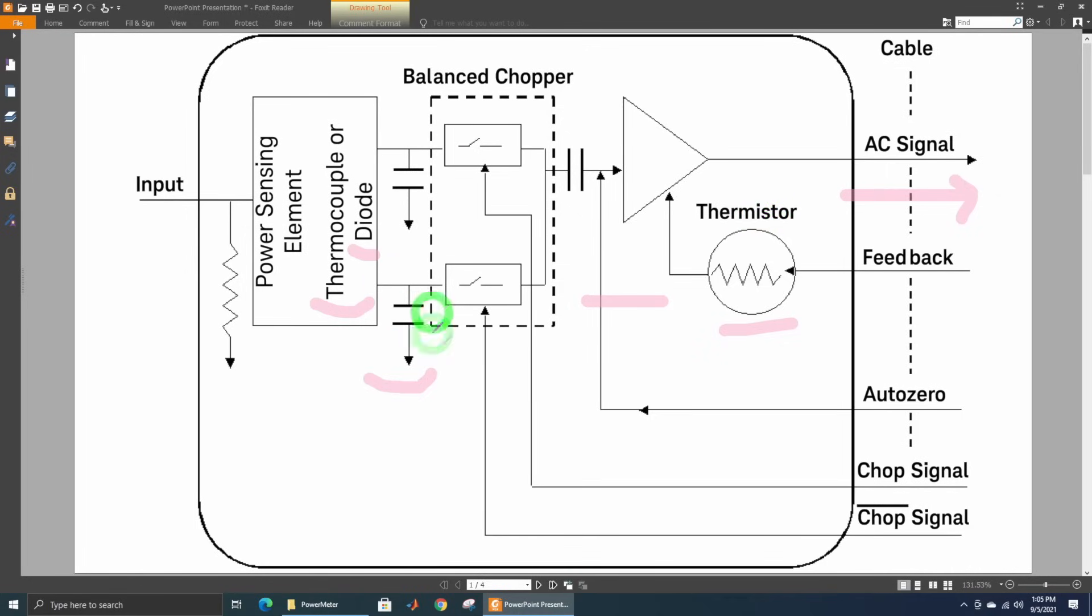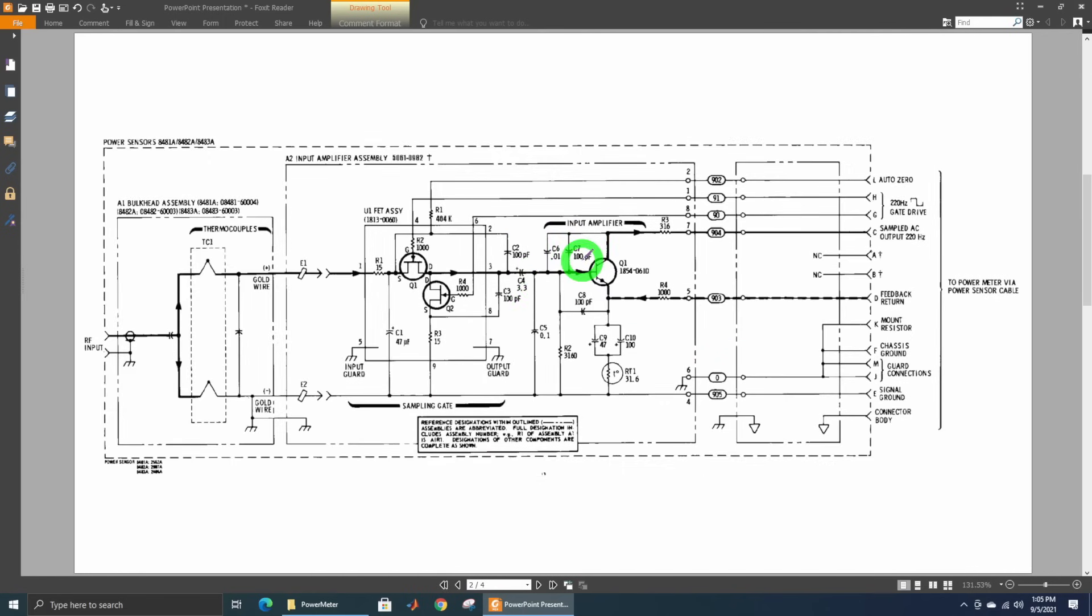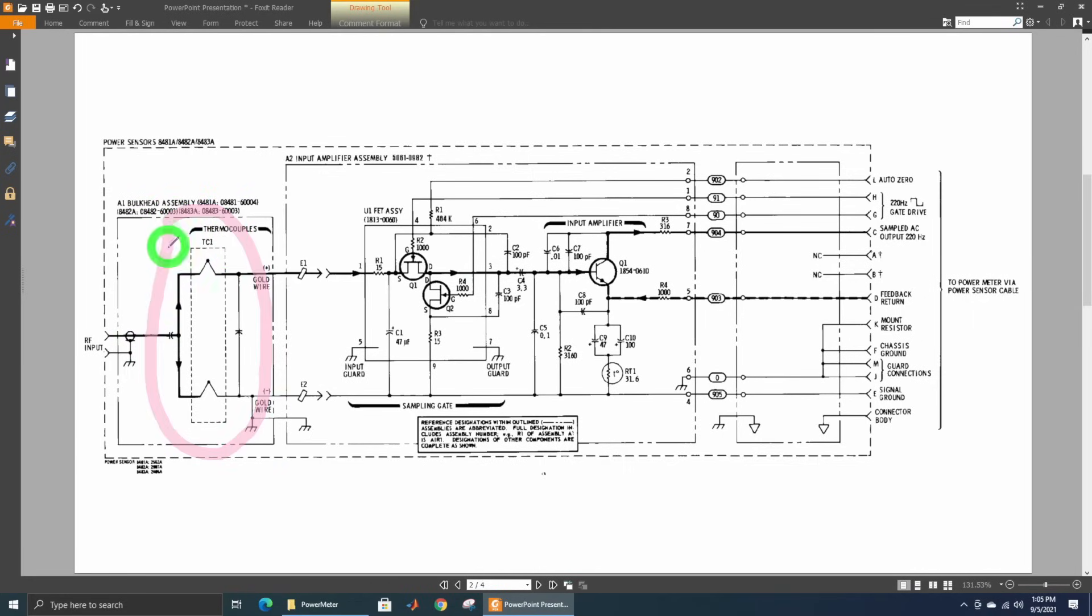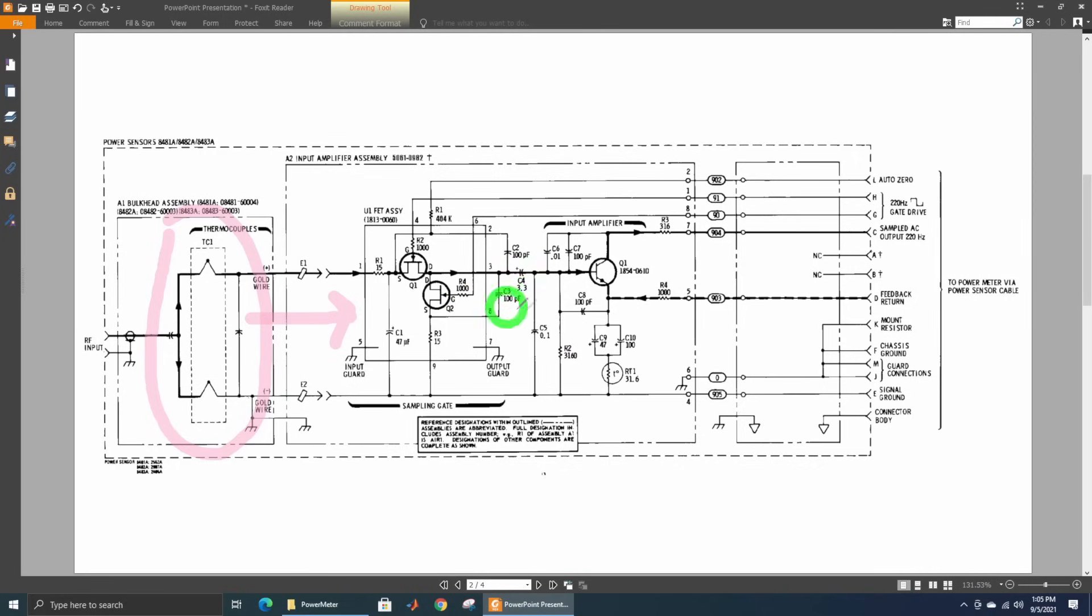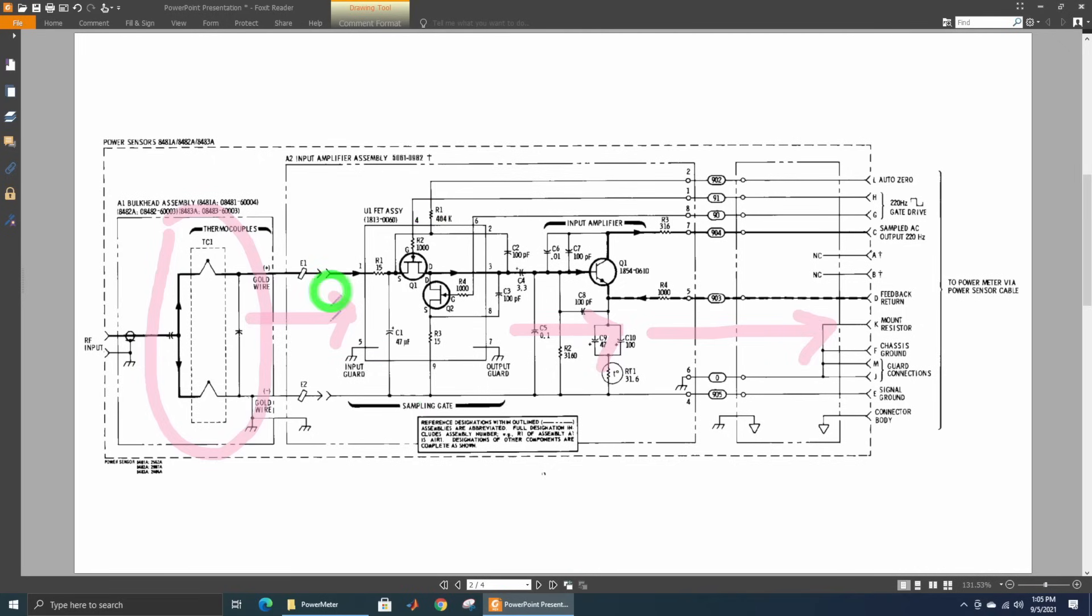These power sensors can be expanded into the complete block diagram or schematic. This is a thermocouple version. You can see the thermocouple here, measured using classic thermocouple behavior. It goes into this chopper amplifier, then into this AC amplifier, and finally going out. This is what you'd find in a thermal-based, thermistor-based, or thermocouple-based power sensor.